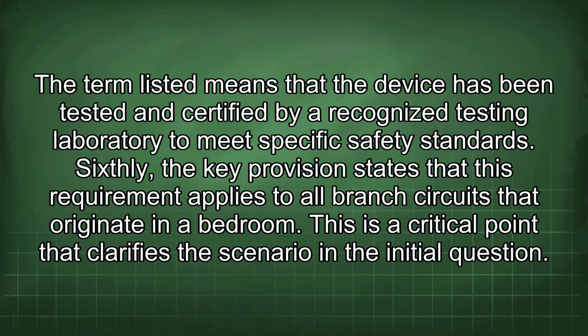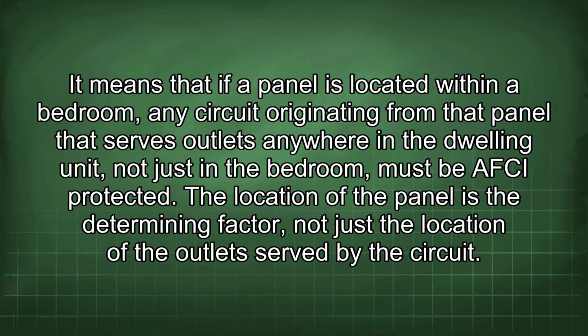Sixthly, the key provision states that this requirement applies to all branch circuits that originate in a bedroom. This is a critical point that clarifies the scenario in the initial question. It means that if a panel is located within a bedroom, any circuit originating from that panel that serves outlets anywhere in the dwelling unit, not just in the bedroom, must be AFCI protected. The location of the panel is the determining factor, not just the location of the outlet served by the circuit.